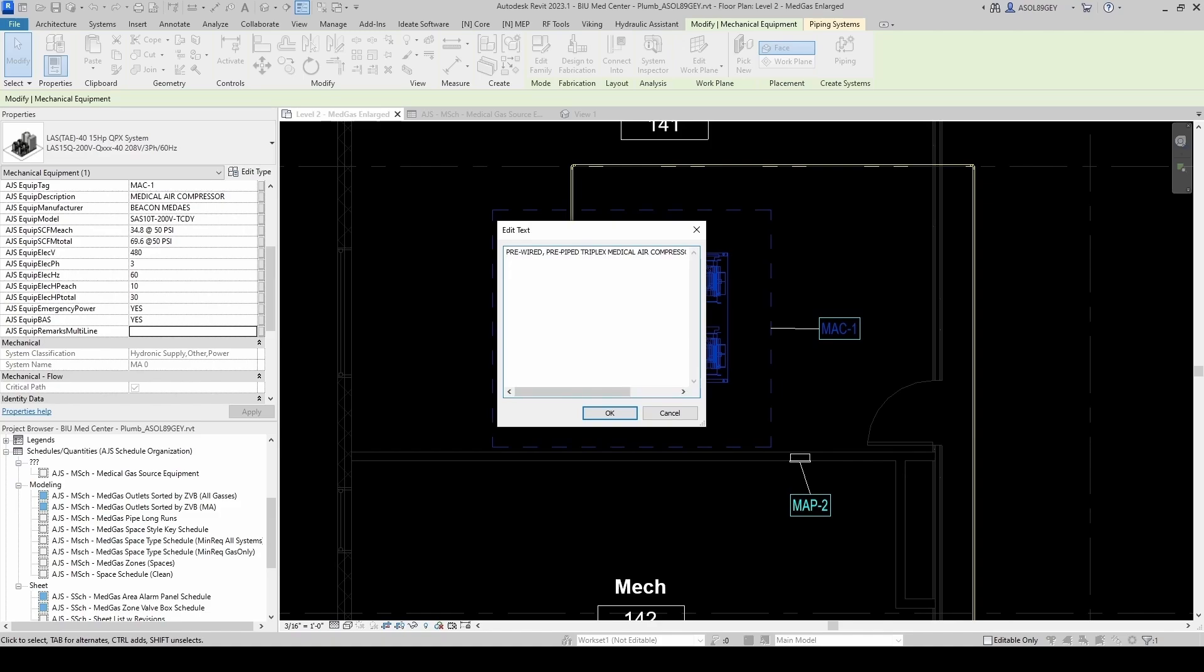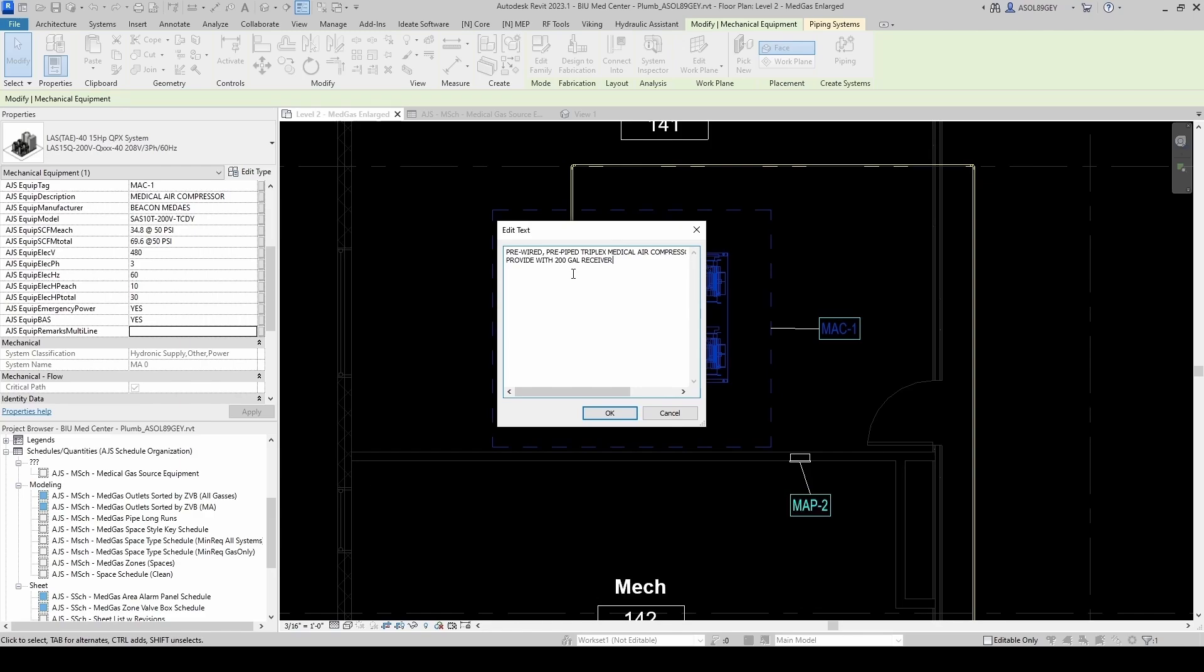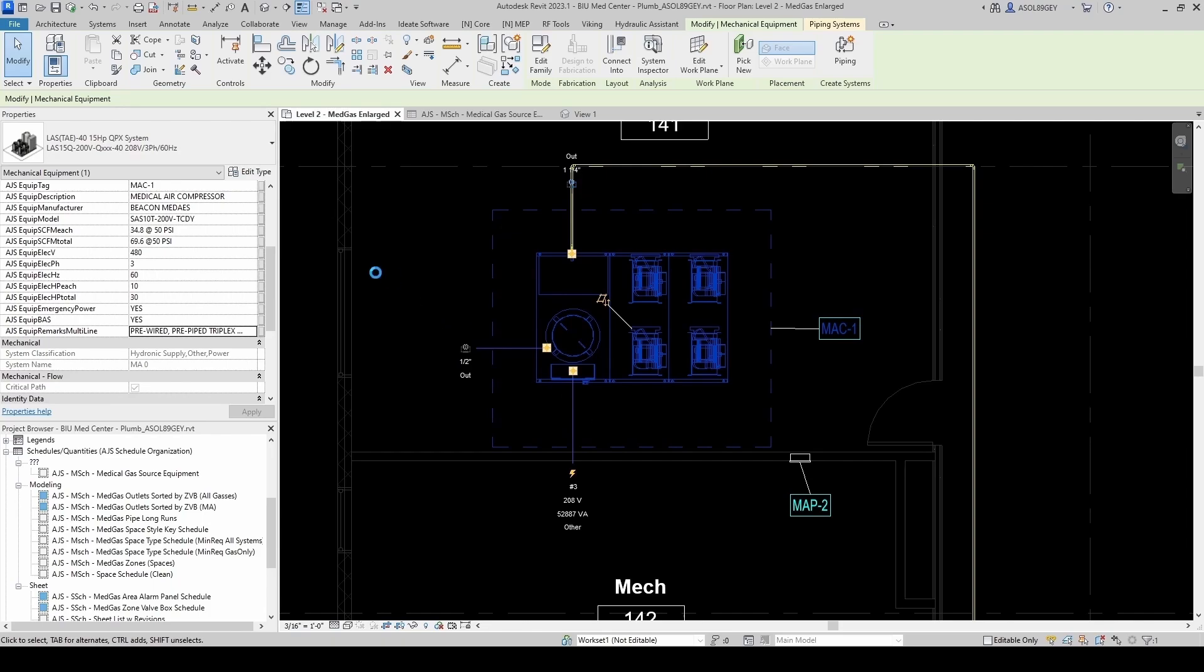And now I can hit Enter and go to the next line if I wanted to. So provide with 200-gallon receiver. Could have this as a separate column as well. Actually, I think it would have been nice. I might change it in the future. You can provide with 4-inch concrete housekeeping pad and spring isolators. And then we want the entire system, entire packaged system, shall be listed and NFPA 99 compliant. And you know, many of this could be footnotes. But I don't like depending too much on footnotes because Revit is not too friendly when it comes to schedules and footnotes. And you'll see why in a little bit.